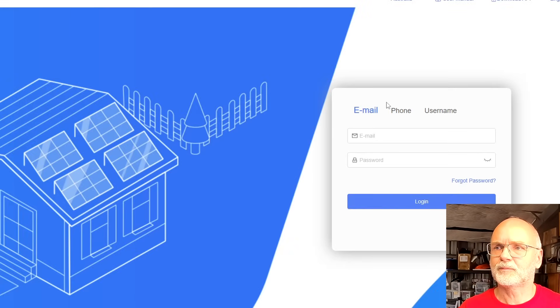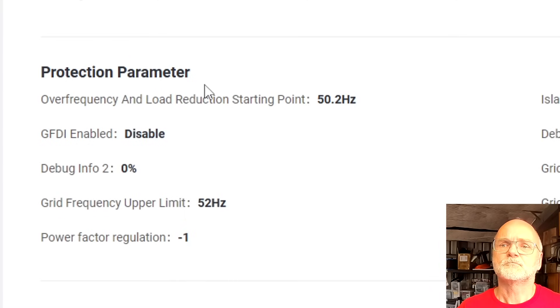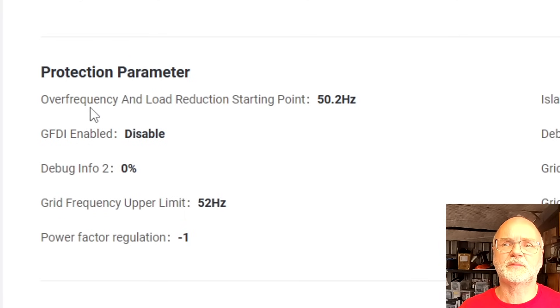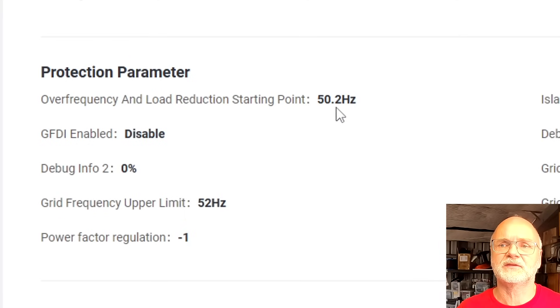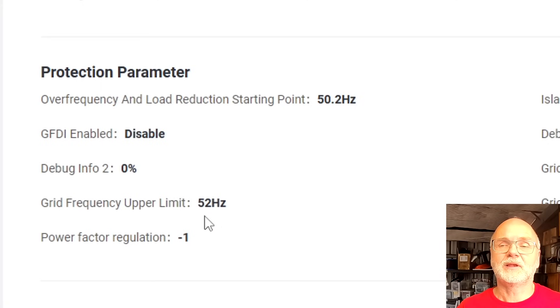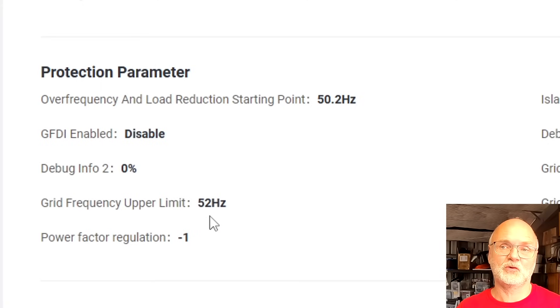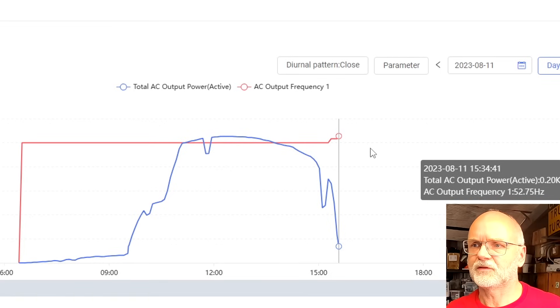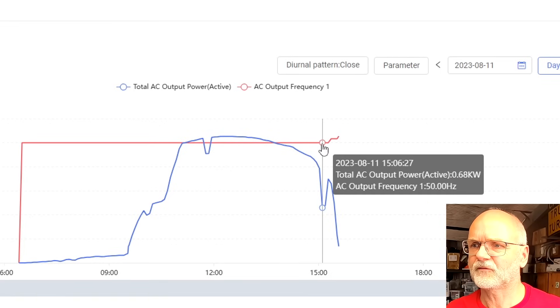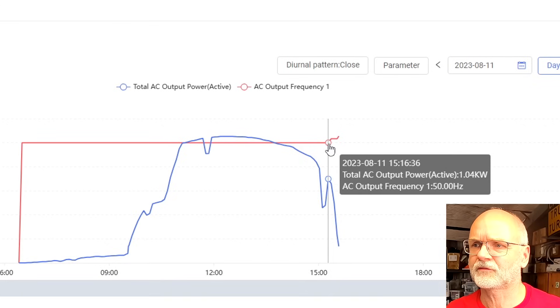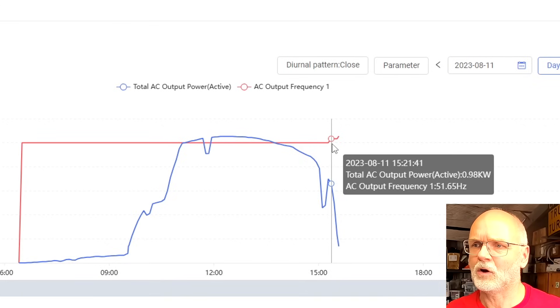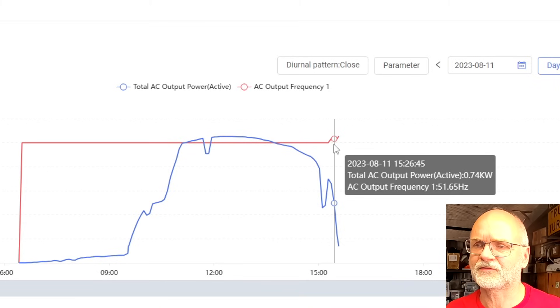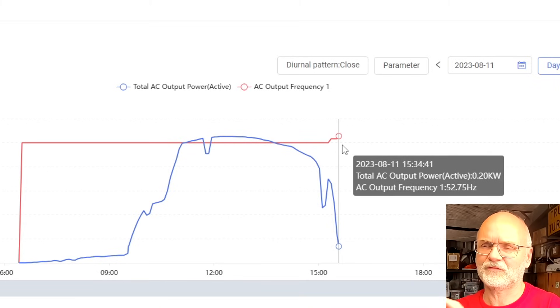Let's see if we can find anything in the app portal of the Solarman. Here it says over frequency and load reduction starting point is at 50.2 hertz and the upper limit is at 52 hertz, so whenever we reach 52 hertz it turns off altogether. Here we can see the red curve is our grid frequency at 50 hertz and then it increases, and you can also see the power output decreases at the same time. These are the same curves from the micro inverter perspective.